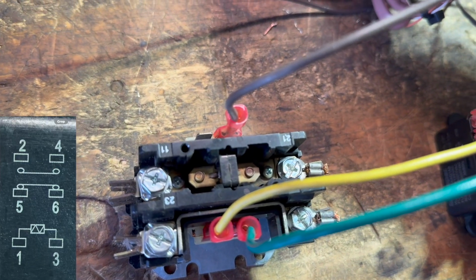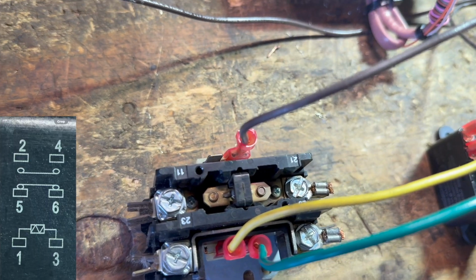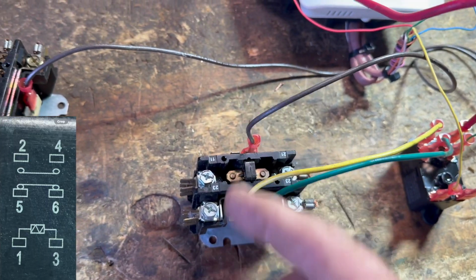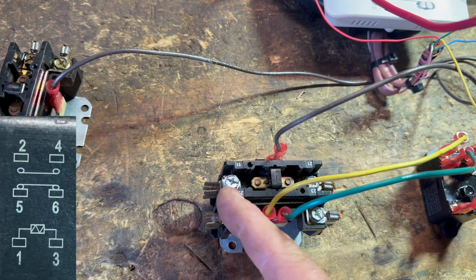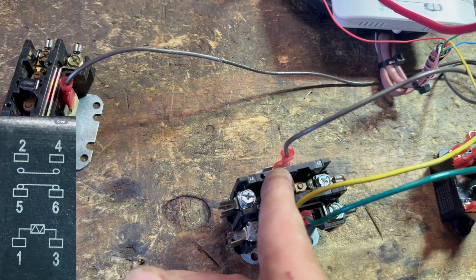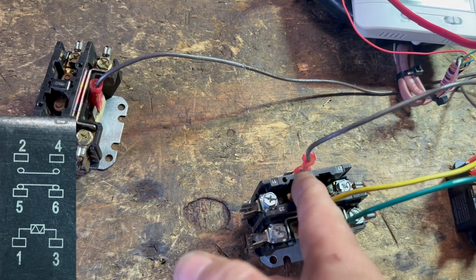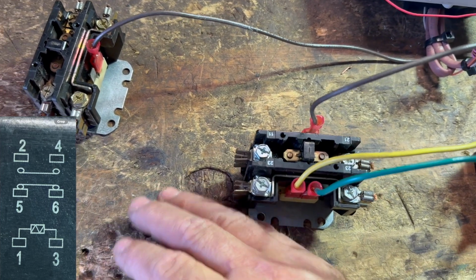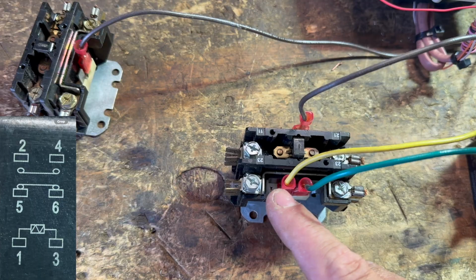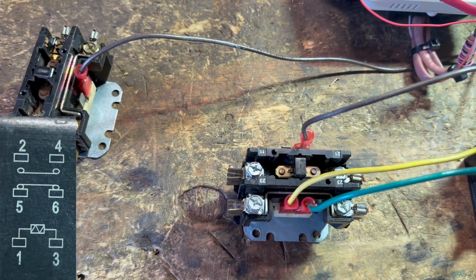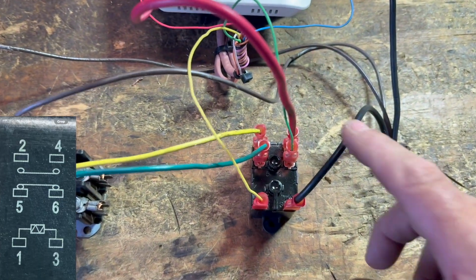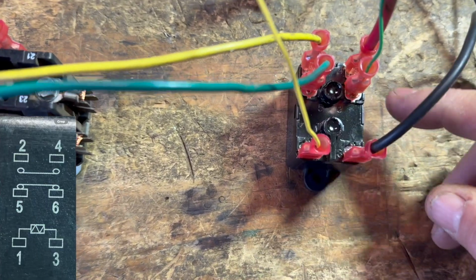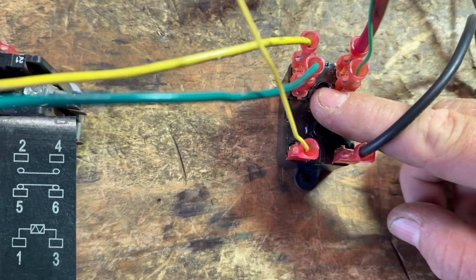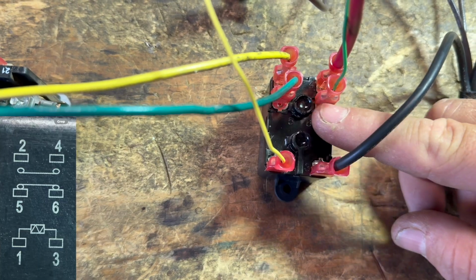Okay, I'm going to turn it back to auto now, turn it back this way, make the call for fan stop, and you can see it released the load. So normally here you'd have high voltage coming in here, but it wouldn't be able to get through until this is sucked in. That's a contactor. All right. And it's sucked in via 24 volts. So it needs hot 24 volts here and a common over here. So between numbers 5 and 6, we are normally closed. So the circuit will go right through.